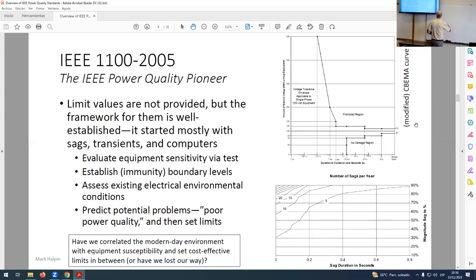It is represented in these two graphics. This graphic at the top, you may know, is the modified version of the so-called CBEMA curve. We call this the ITIC curve now. This represents the sensitivity of computer electronics to voltage. That's a sensitivity curve. This graphic gives us a visual indication of the length of voltage sags, the depth of the voltage sag, and how often they occur at a particular location in a power system.